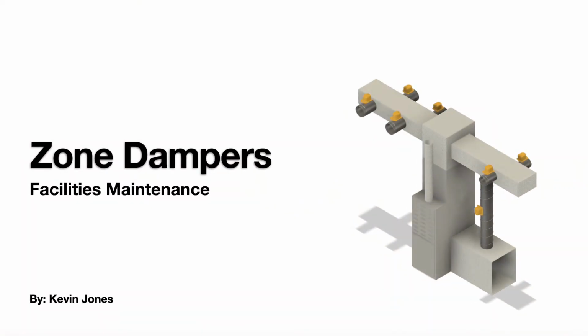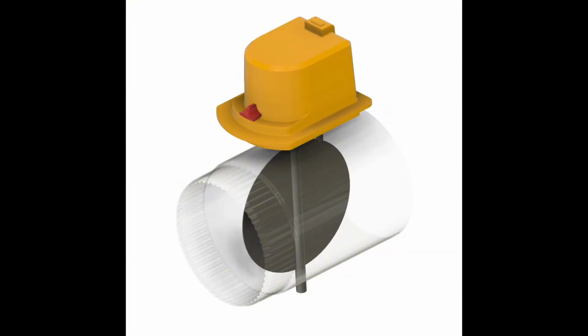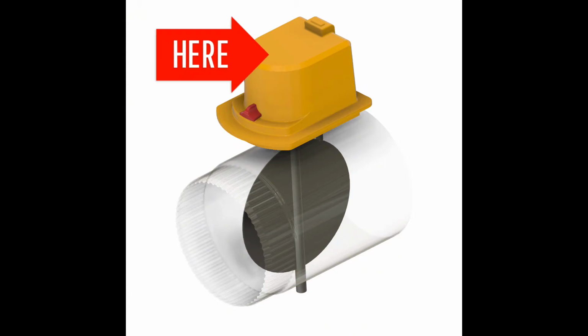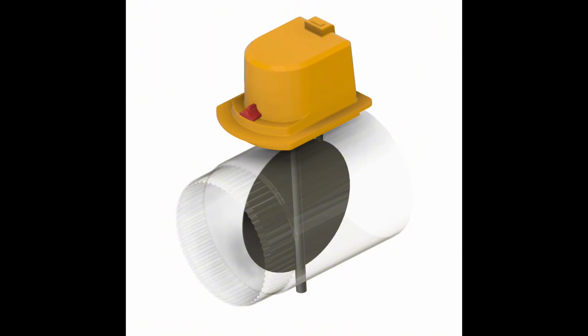Okay, today we are talking about zone dampers. What is a zone damper? This is a zone damper. They come in different sizes depending on the size of your ductwork. There's an electronic actuator, usually operated on 24 volts, that moves the damper inside the duct that you see here. And there's usually some sort of adjustment lever or set screws that will control how far that damper can travel. So do you want to close all the way, halfway, etc.?